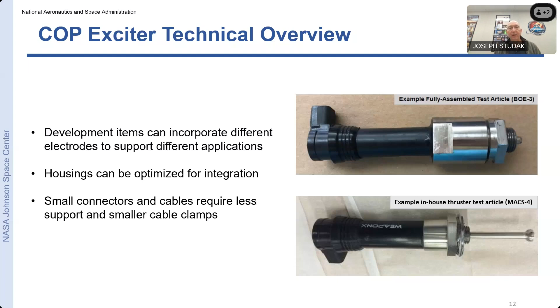The smaller connectors mean it's a much easier device to integrate, because you don't need as much volume now just for the connector and access to the connector as you used to. Here's a couple of different versions that we built. One does not have its electrode tip installed, the other one does. You can see there's slightly different housings as we iterated through our development cycle and came up with variations on the theme that would support different applications. Chart, please.